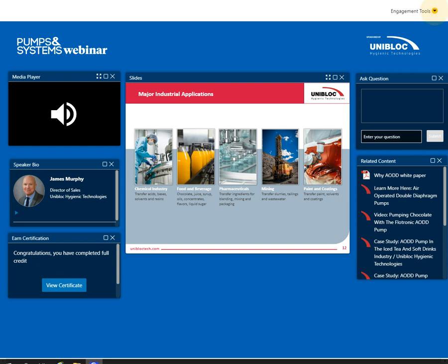In that case, that's going to require a diaphragm pump that is constructed out of stainless steel and typically polished to a 16 RA. And RA stands for roughness area. Essentially what roughness area is, to get very detailed there for a second, is how many imperfections are in your stainless steel in a 1 inch by 1 inch square. So the least amount of imperfections, the lower the number.